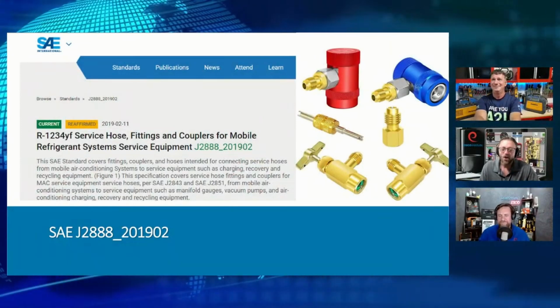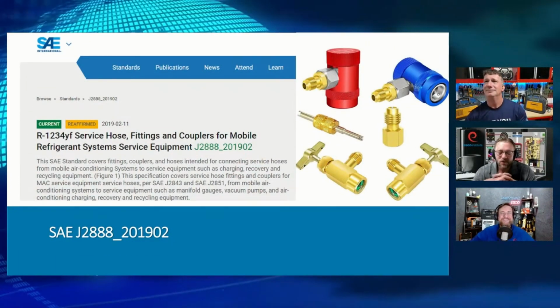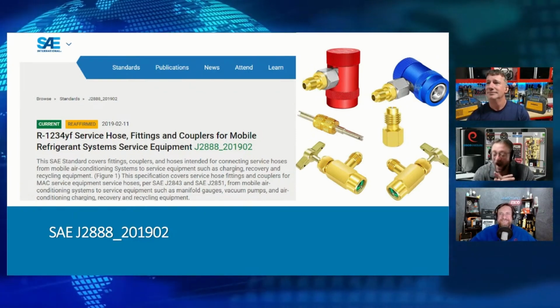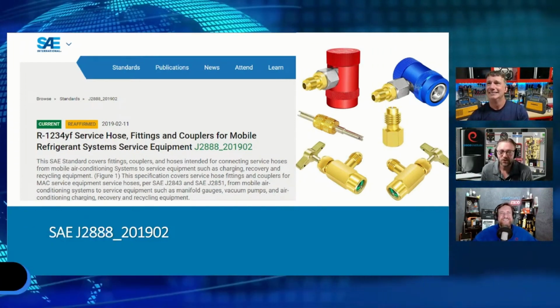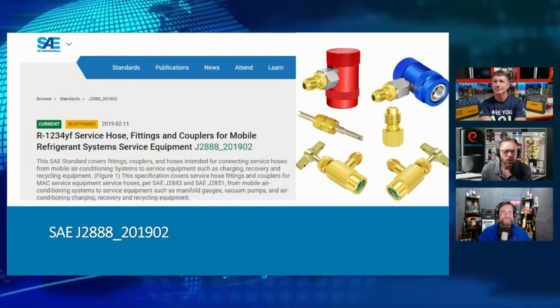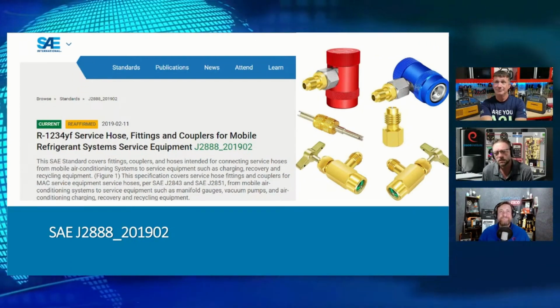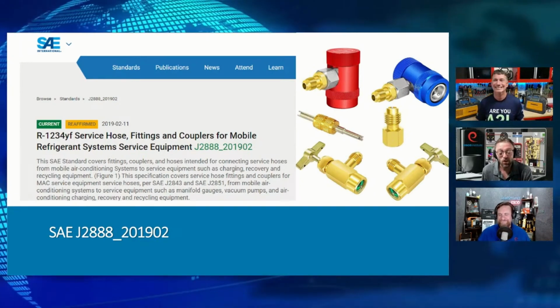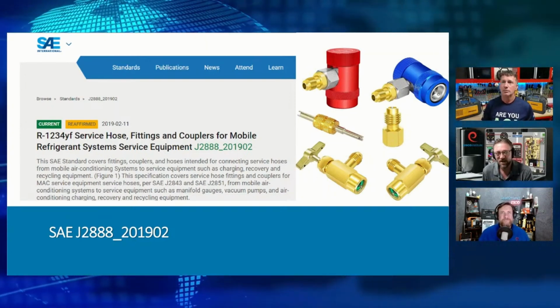And go. All right, so I've been doing quite a bit of training: students, teachers, technicians, a whole bunch. And one of the common myths that gets presented to me is, "I heard you can't braze with these flammable refrigerants." That's such a good point. And my question to them is, well, how much brazing do you do with the refrigerant in the line? I try never to. All right, because when we're brazing a system, we're purging nitrogen, and the system is empty. So I don't see the problem there.